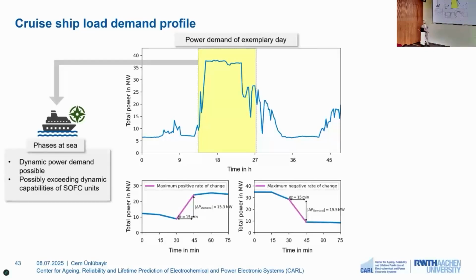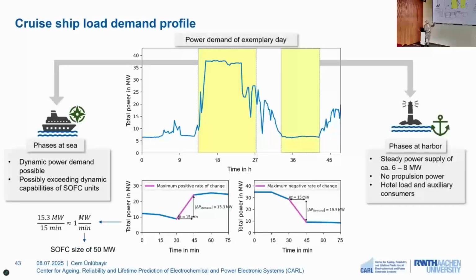We have actually looked at the different ramps we've seen. You can see on the bottom two plots the positive rate of change, the maximum, and the negative rate of change. When we look at the ramp up, which is actually lower in absolute terms, we're talking about circa 1 megawatt per minute. And if we think about this, the SOFC can at maximum change its power output at 2%, which is also an important figure. We would come up with an SOFC size of 50 megawatts, so you can already see that if you put 50 megawatts on this chart on top, you would probably overdimension your system a bit too much. That's why the battery is highly beneficial, to not overdimension.